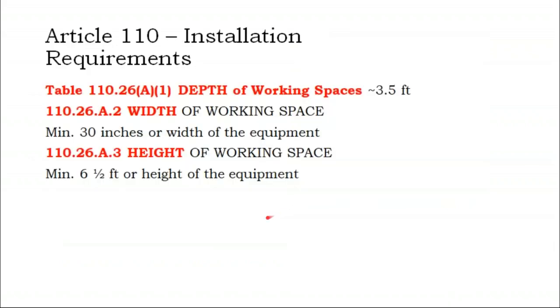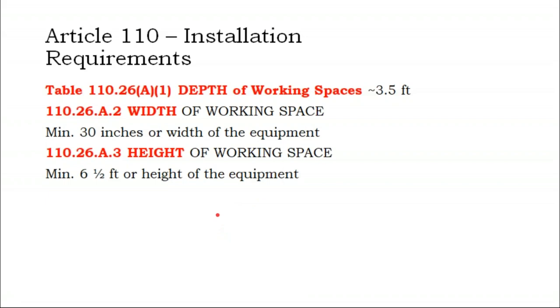So I think the main thing is that solar installers or solar designers are used to dealing with one small inverter for the entire system, but now you might have one battery inverter today, three battery inverters tomorrow if you want to, maybe do a critical load backup today and a full off-grid conversion in the years to come. And all of these components will need a 3.5-foot working space in front of them, and a 6.5-foot tall working space in front of them.